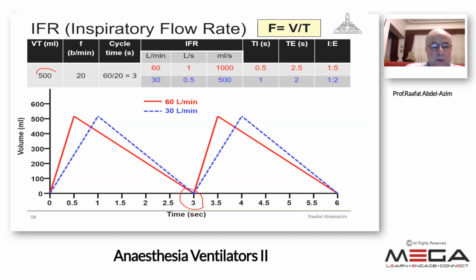If I give a tidal volume of 500 milliliters, and the rate is 20, this means that the respiratory cycle time is 3 seconds. It is divided into inspiration and expiration. Having 500 milliliters to be given in half a second means that 1 liter will be given in 1 second. 500 in half a second means 1 liter in 1 second. So the inspiratory flow rate here is 1 liter per second, because that is 60 liters in a minute. So it is 1 liter per second, 1,000 milliliters per second.